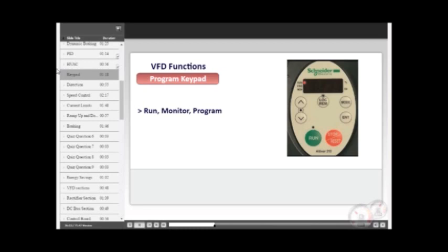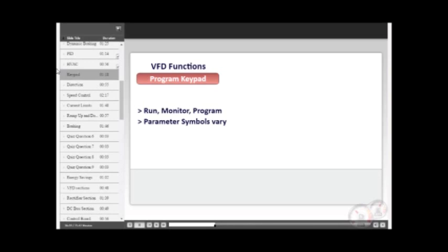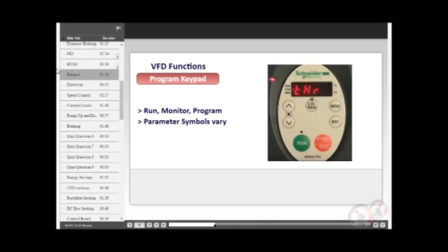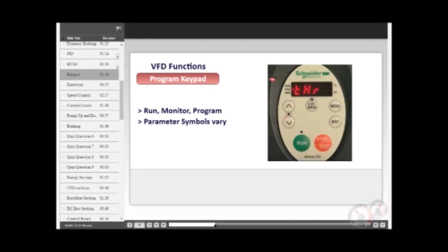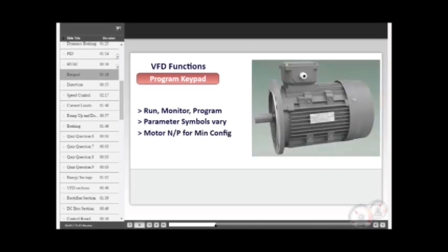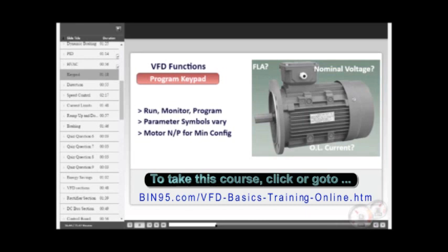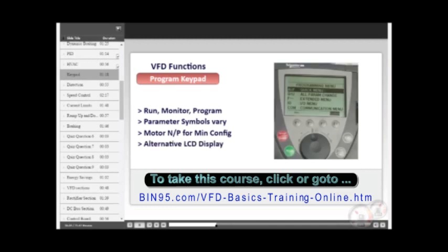It is important to note that the symbols used for programming may vary between manufacturers. In this instance, the Schneider Altivar 212 uses the symbol THR for inputting the thermal overload value. Most drives can be set up very easily for routine applications by inputting information from the motor nameplate, namely, full load current, motor nominal voltage, and desired overload current level, which in most cases may be the same as the full load current of the motor. Many manufacturers offer an alternative LCD keypad with English text that spells out the function rather than provide a symbol. In most cases, these can be interchanged with the standard supplied keypad or as a remote mounting kit. Coming up, we'll talk about the other VFD functions available for most drive manufacturers.